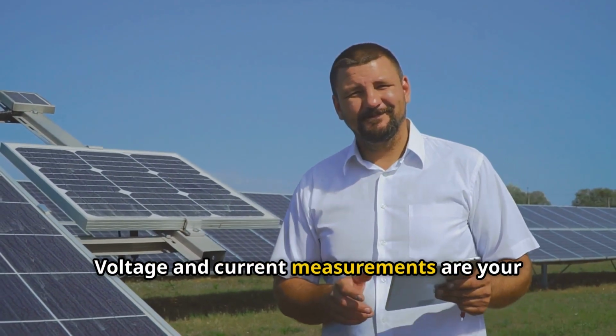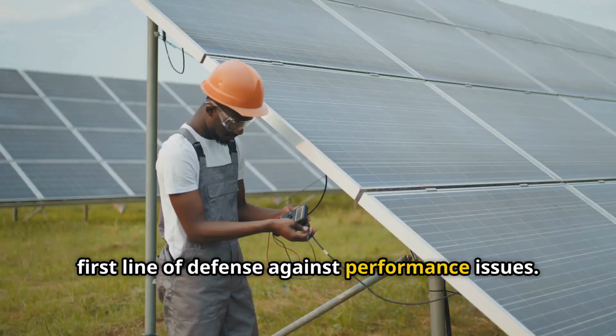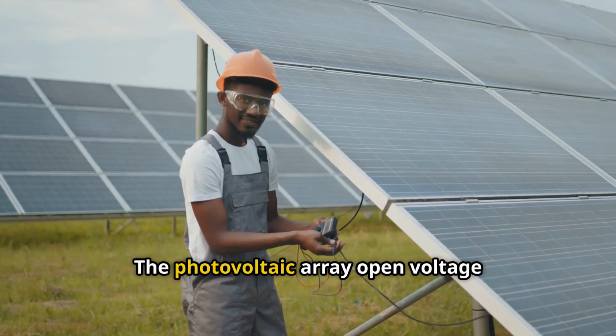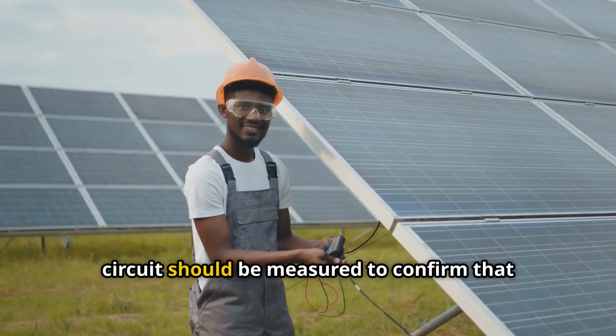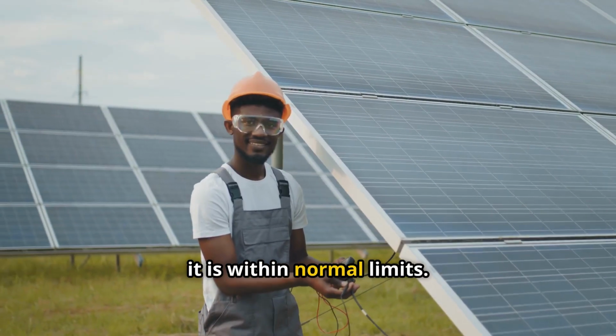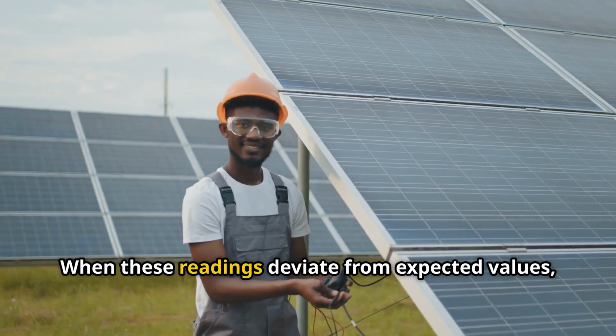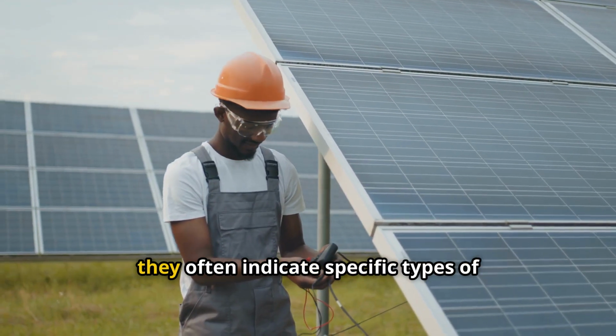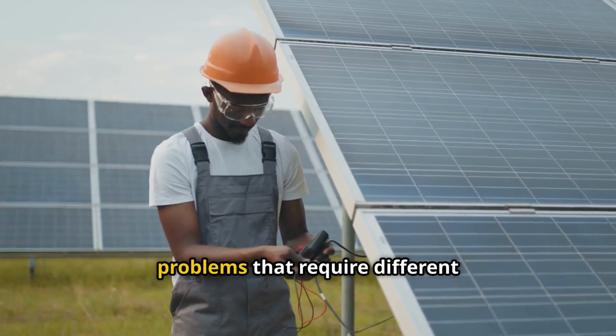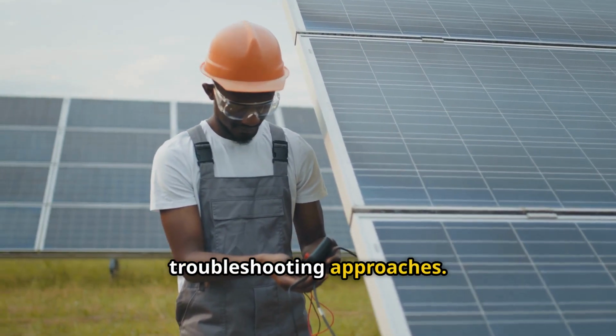Voltage and current measurements are your first line of defense against performance issues. The photovoltaic array open-circuit voltage should be measured to confirm it's within normal limits. When these readings deviate from expected values, they often indicate specific types of problems requiring different troubleshooting approaches.